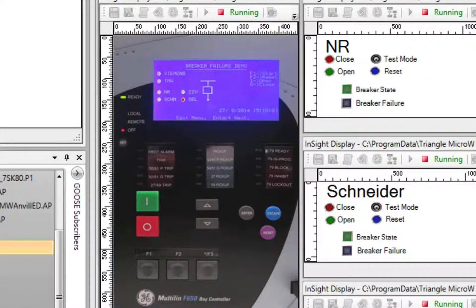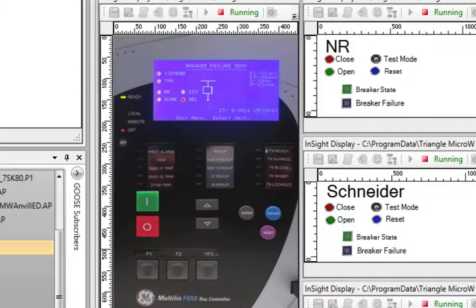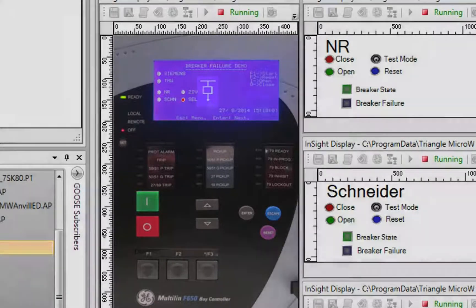Note the GE device which uses an image of the actual device. Insight controls and displays have been overlaid on this image. As the data attribute in the IEC-61850 object model is updated, the corresponding Insight display element is updated, providing a simulation of the device's display. Note that the elements include the breaker status, which is now shown as open, and a fault indicator, which correctly shows that the fault originated with the Schweitzer device.